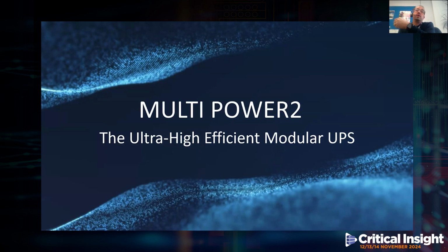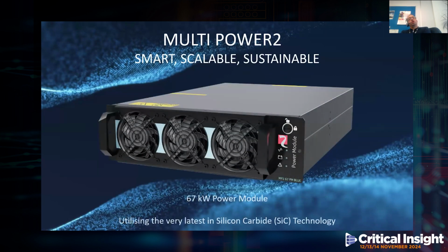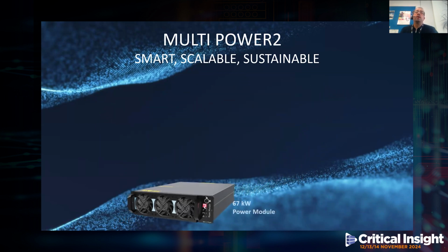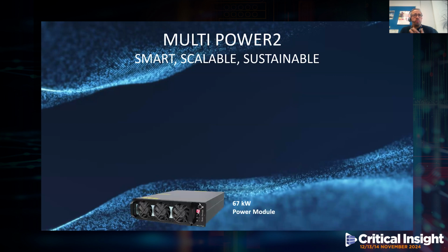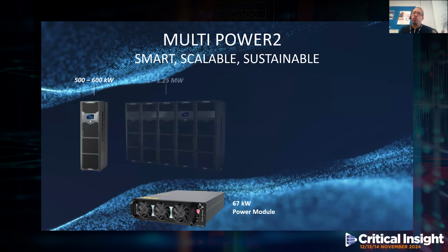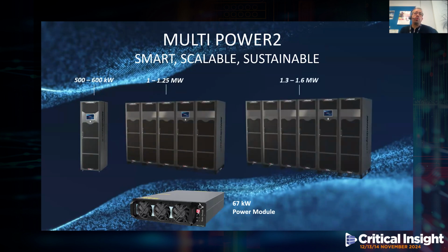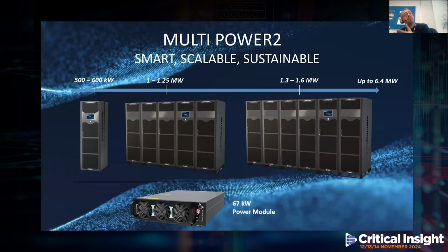Multi-Power 2 is effectively an ultra-high efficient modular UPS system. Now, like all modular UPS, the key building block is the actual power module itself, and the Multi-Power 2 is no different. It is built using a 67 kilowatt power module, which utilizes the very latest in silicon carbide technology. Now, this state-of-the-art module is coupled with three main power cabinets. The ones that we have available are the 500 to 600 kilowatt cabinet, the 1 to 1.25 megawatt cabinet, and the 1.3 to 1.6 megawatt cabinet. And Multi-Power 2 can also be expanded up to 6.4 megawatts by paralleling multiple cabinets together.